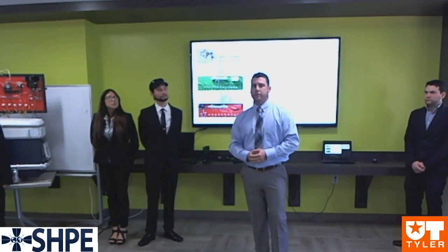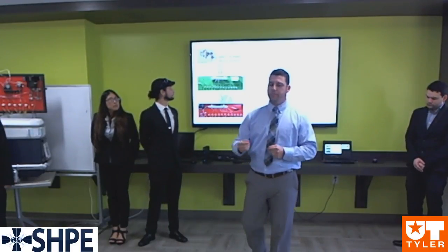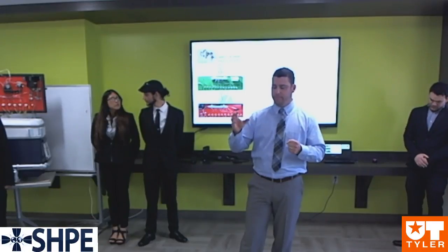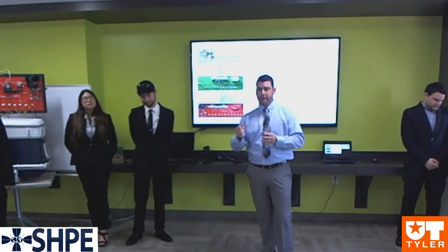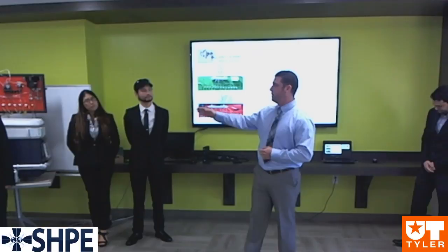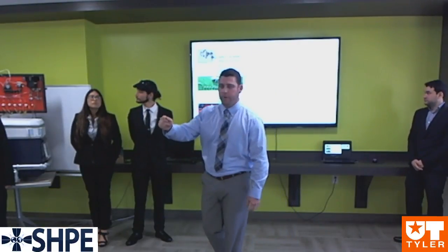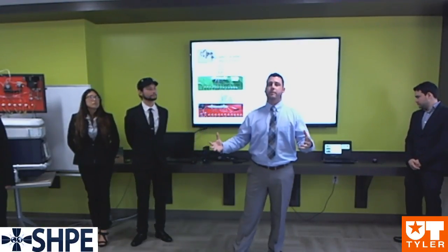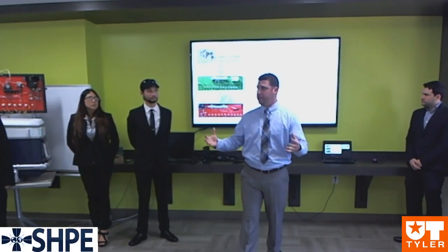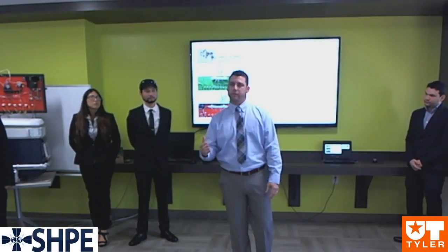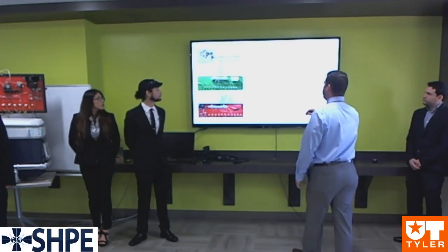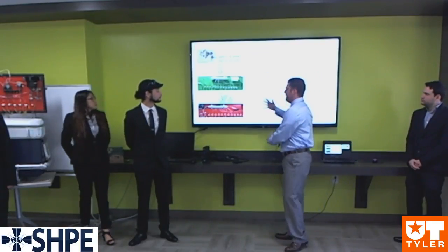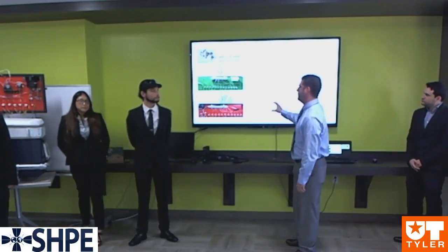Well, the solution actually was quite simple in that we bought a cheap medical air regulator. You can dial it into exactly whatever you want. So on the front end, you can put it right at 10. So we have a copious amount of air coming in that we don't need to worry about having a good supply of air, and we can regulate it to exactly the flow rate that we need. You can see here in this picture aesthetically how we progressed from where we started to the end result.